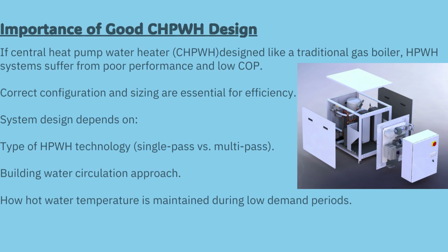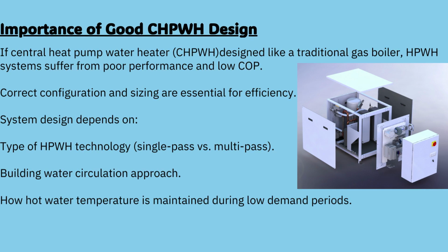Good system design is the foundation of a successful central heat pump water heating system. If a heat pump water heater is designed and sized like a traditional gas boiler, the building owner will end up with functional problems and poor performance. So, what does good design look like? It starts with choosing the right system configuration.